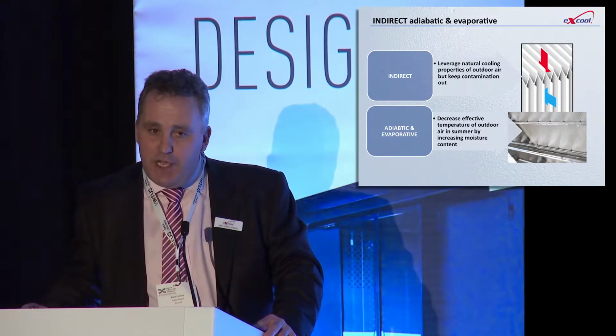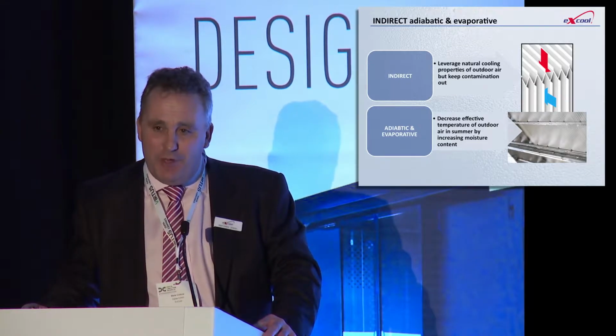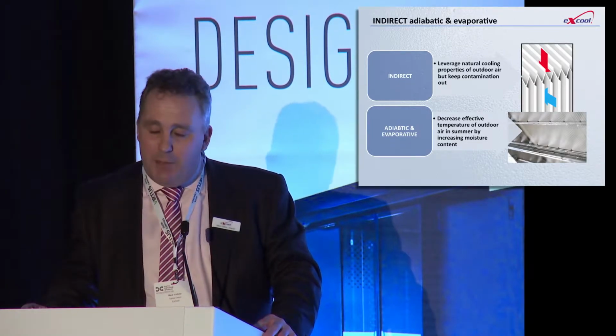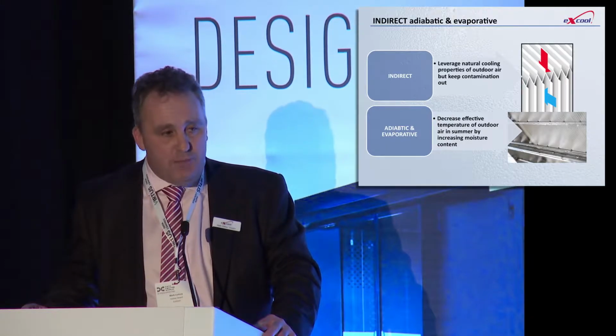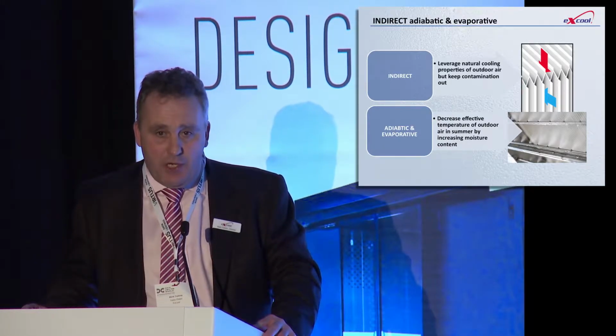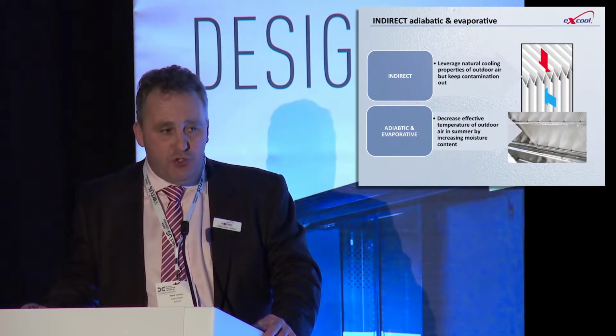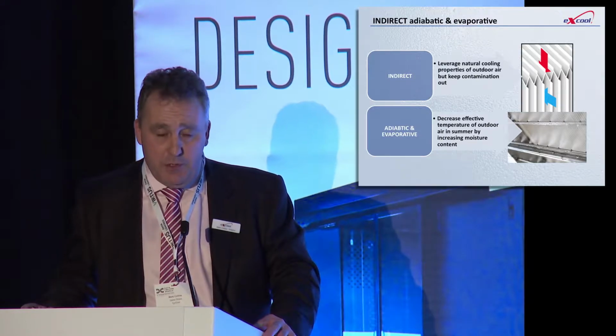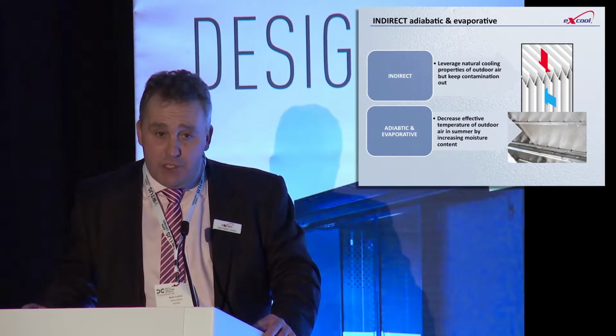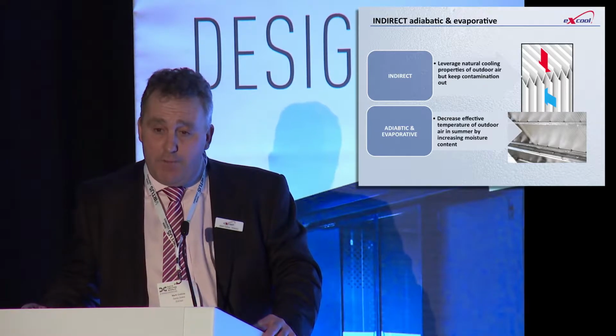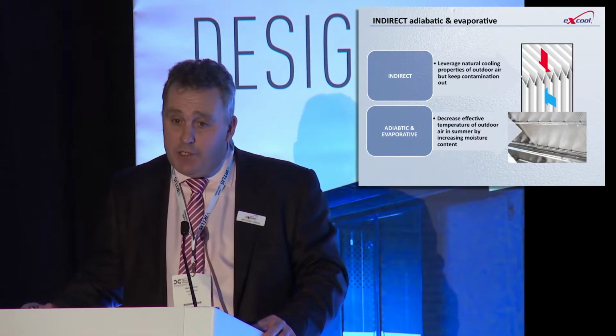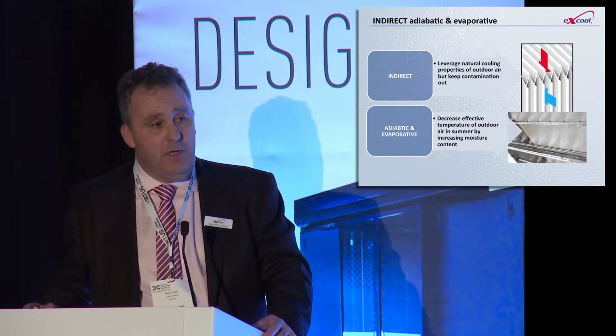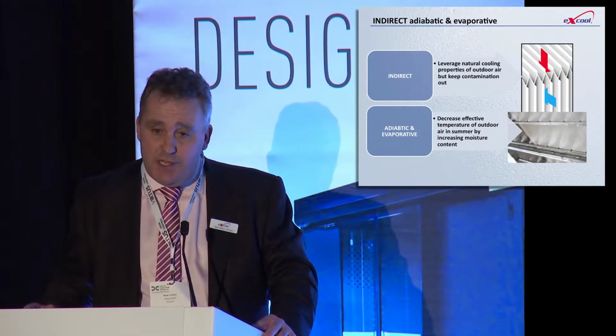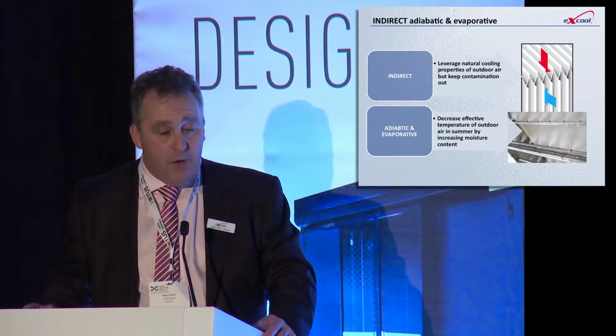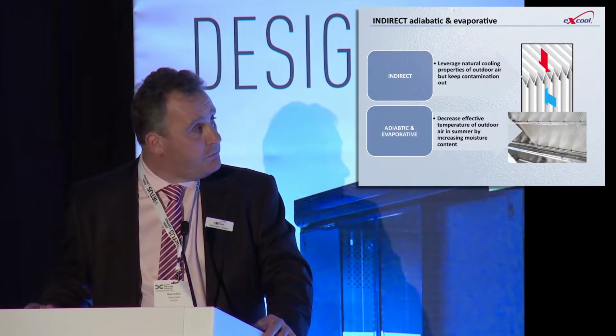In the middle of summer, when things get a little bit warmer and it gets a bit more difficult to achieve that, we introduce our adiabatic and evaporative system, which introduces moisture into the outdoor air stream only. That has the effect of lowering the outdoor air temperature from its dry bulb temperature to its wet bulb temperature, which generally speaking in the UK, for instance, will reduce the temperature from 35 degrees C down to maybe 21 degrees C. And it's that we use as a cooling medium to introduce air into the data center within the ASHRAE TC 9.9 recommended environmental envelope.